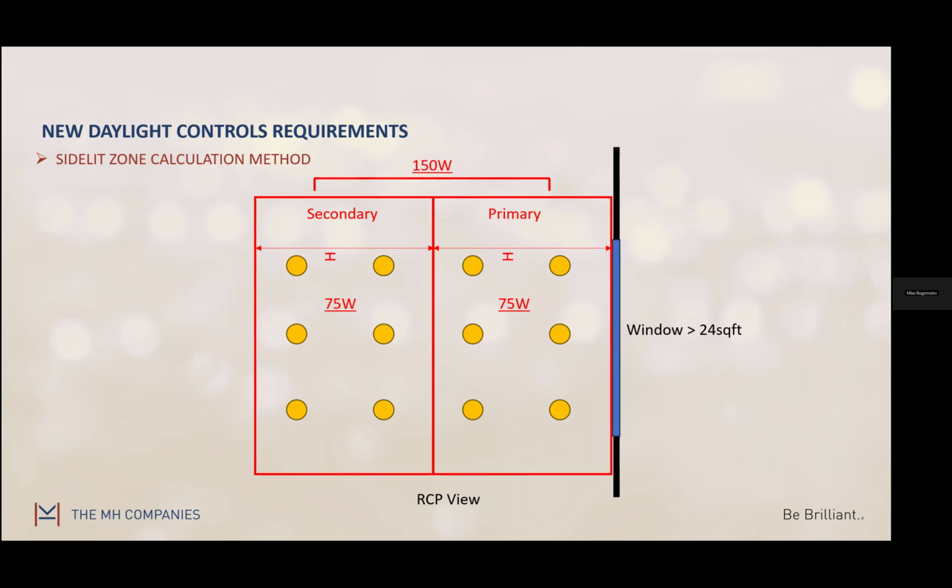If you're just trying to hit that check mark and it's a very small space, you only have one office and it just has to meet the code, you could do that. I think those devices typically would be a separate switch from the actual receptacles. Sometimes they have the receptacle built into that switch. But in that case, a lot of times you'll end up losing your unswitched receptacle for that specific receptacle that you're putting that device into. So just something to keep in mind.